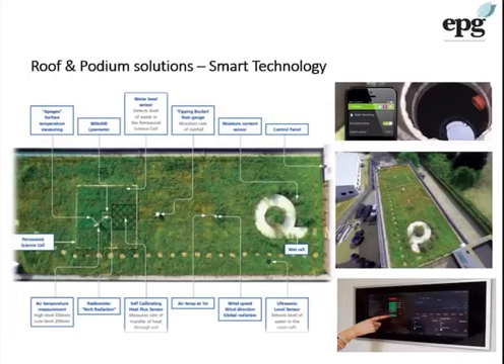and for storage within the same volume build-up. So traditionally, with an orifice plate limiting the flow rate, the passive irrigation volume used to have to be separate from the attenuation volume, because the attenuation volume needs to half empty within a 24-hour period. So it's ready to deal with the next storm. So in essence, you needed to get as much water off as possible. So you had to have two completely separate systems.